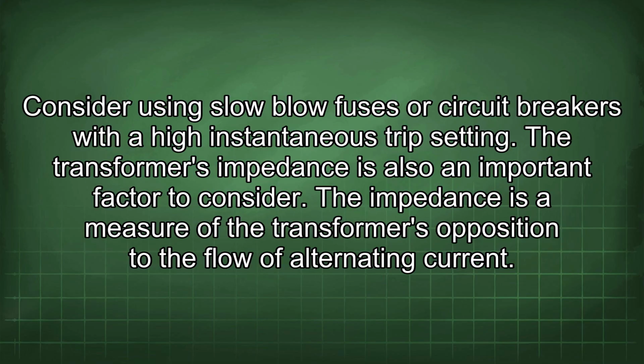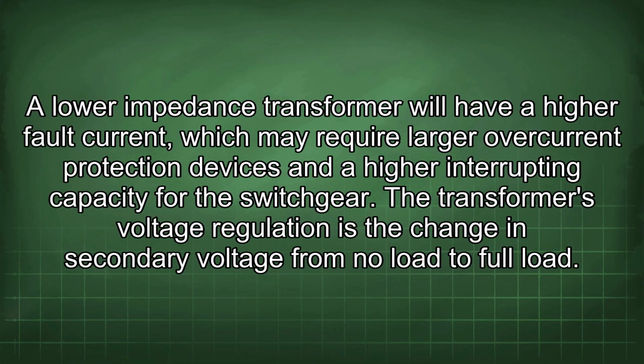The transformer's impedance is also an important factor to consider. The impedance is a measure of the transformer's opposition to the flow of alternating current. A lower impedance transformer will have a higher fault current, which may require larger overcurrent protection devices and a higher interrupting capacity for the switchgear.